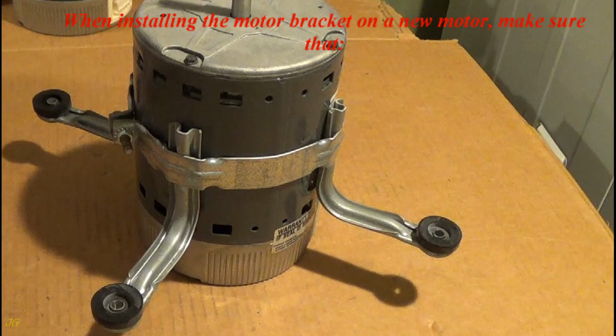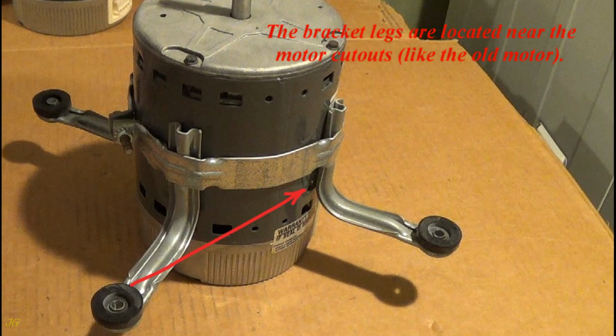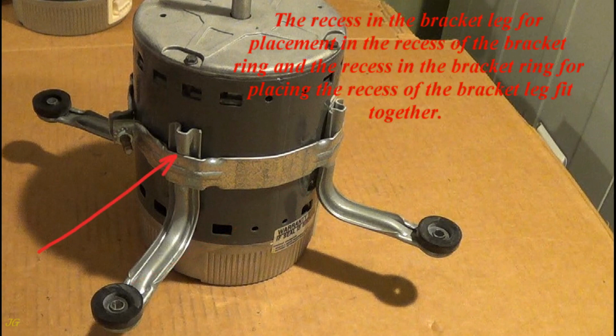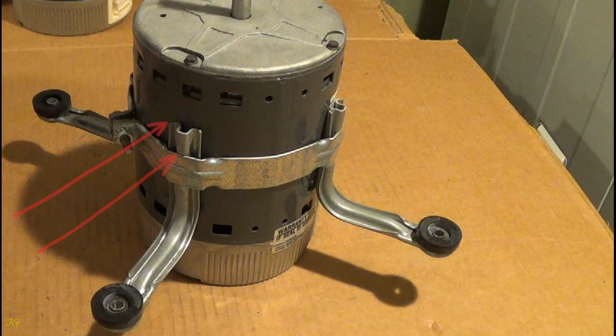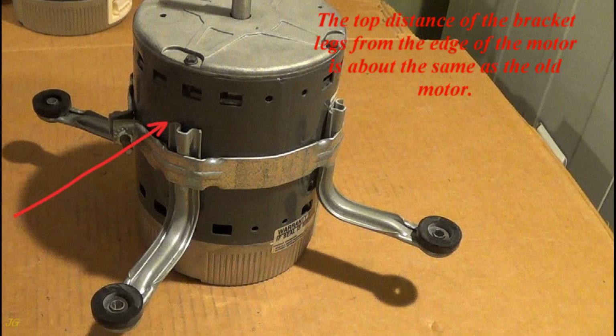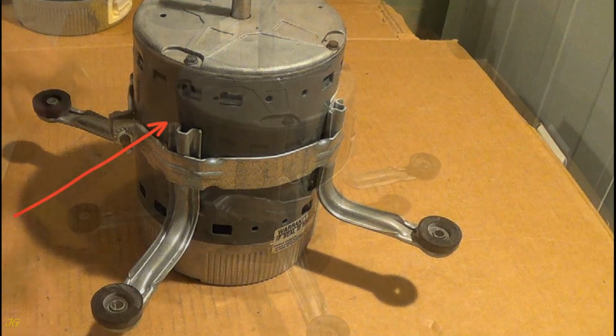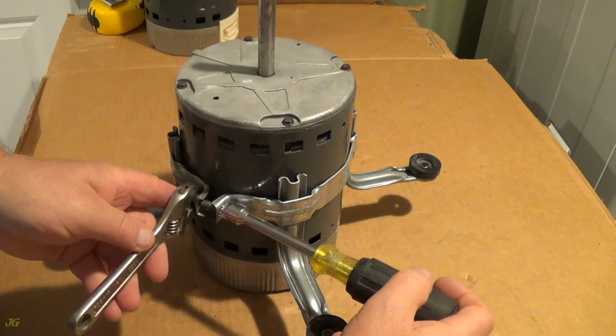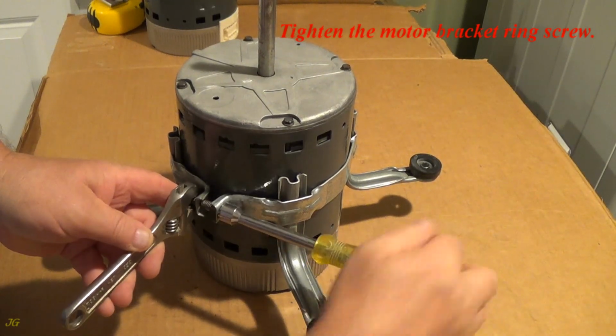When installing the motor bracket on a new motor, make sure that the bracket legs are located near the motor cutouts, like the old motor. The recess in the bracket leg for placement in the recess of the bracket ring and the recess in the bracket ring for placing the recess of the bracket leg fit together. The top distance of the bracket legs from the edge of the motor is about the same as the old motor. Tighten the motor bracket ring screw.